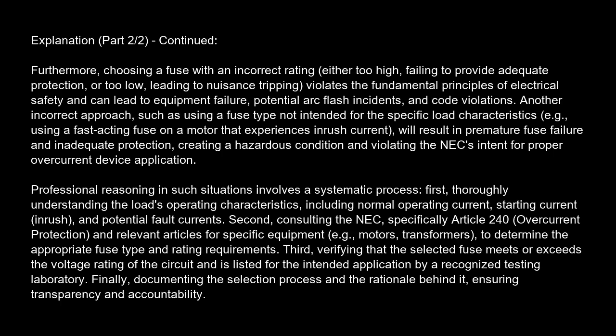Another incorrect approach, such as using a fuse type not intended for the specific load characteristics, e.g., using a fast-acting fuse on a motor that experiences inrush current, will result in premature fuse failure and inadequate protection, creating a hazardous condition and violating the NEC's intent for proper overcurrent device application.